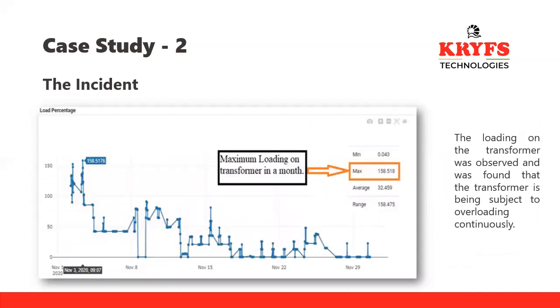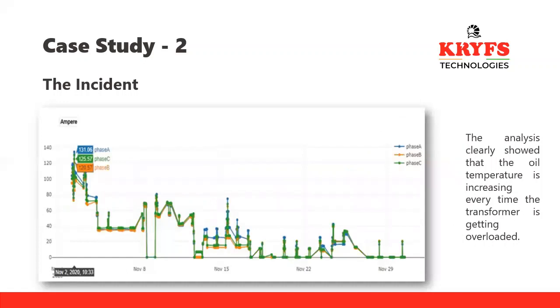The second graphical representation shows that the loading of the transformer was around 158%. This is the actual reason for the failure of the transformer. Even utilities are not able to monitor the actual load of the transformer, but by installing our transformer monitoring device, they were able to see the performance and the load percent. At that time, the maximum load percentage went to 158%. Even in the ampere graphical representation, you can see it went above the threshold value.